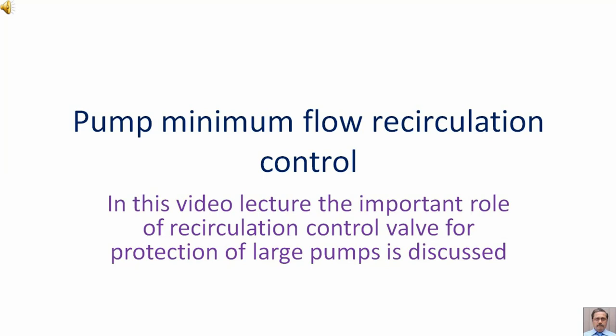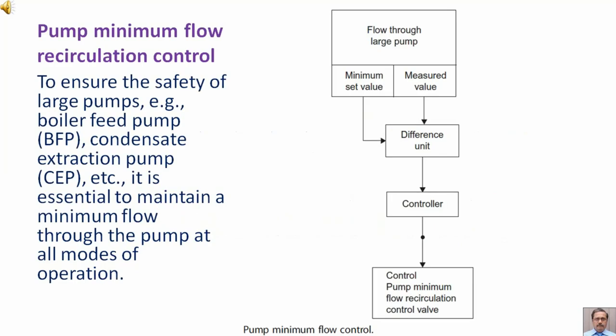In this video lecture, the important role of recirculation control valve for protection of large pumps is discussed. To ensure the safety of large pumps — for example, boiler feed pump, condensate extraction pump, etc. — it is essential to maintain a minimum flow through the pump at all modes of operation.